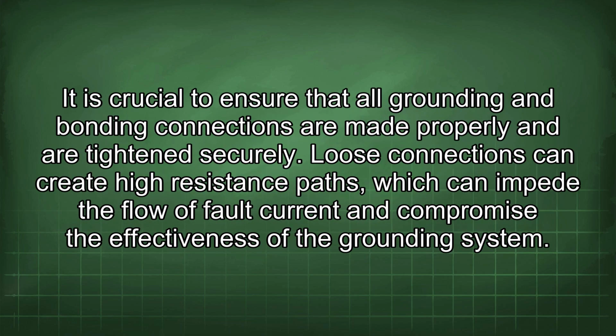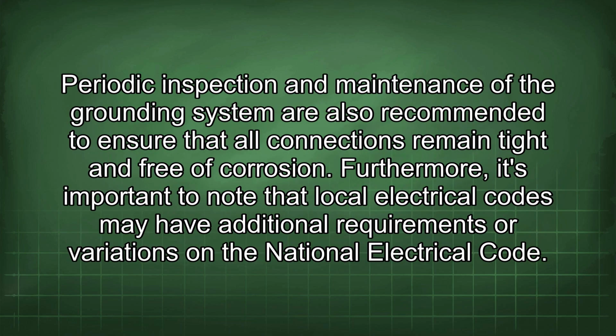It is crucial to ensure that all grounding and bonding connections are made properly and are tightened securely. Loose connections can create high resistance paths, which can impede the flow of fault current and compromise the effectiveness of the grounding system. Periodic inspection and maintenance of the grounding system are also recommended to ensure that all connections remain tight and free of corrosion. Furthermore, it's important to note that local electrical codes may have additional requirements or variations on the National Electrical Code.